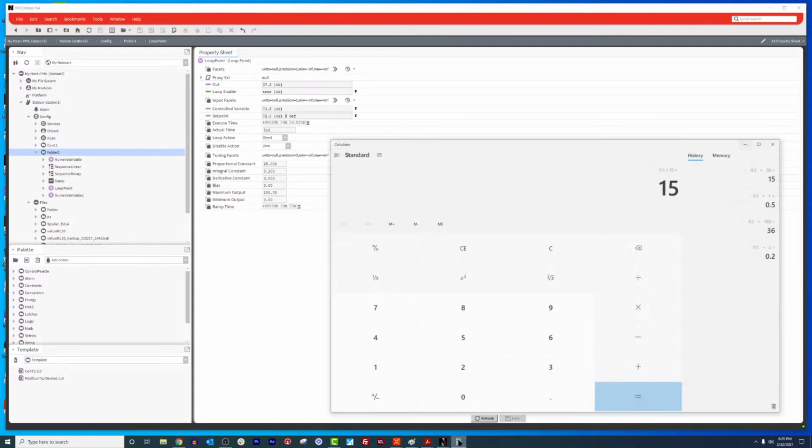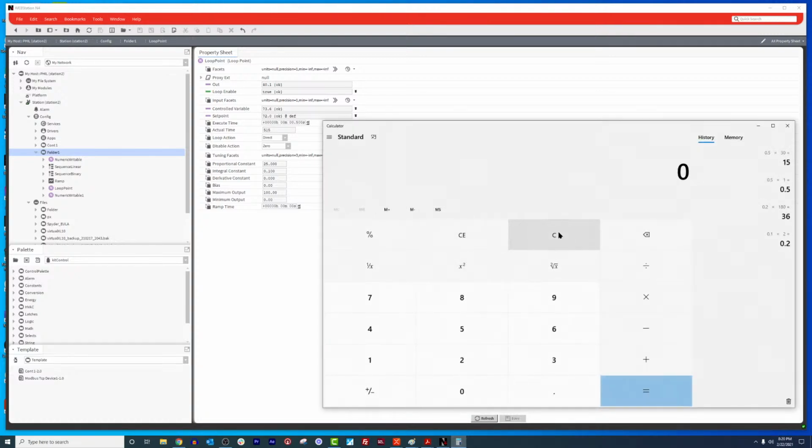But you can do that math that I just showed you a second ago to guide through it. So what I'm going to do real quick is go through that math example again, because I went through it pretty quick and it's important for you to understand. Here's how I did it. I looked at how long it would typically take to saturate, to fully load the loop. For a space loop, maybe we're looking at 180 to 300 seconds.